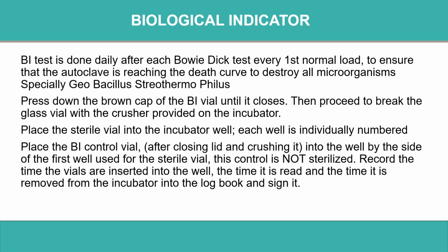After that, record the time the vials are inserted into the well. Actually, incubators have different times to show the result. Like we are using a 1 hour incubator; it will show the result after 1 hour. But in other areas, other hospitals, some are using 3 hours, some are using 8 hours. So it depends on the incubator and it depends on the vial, which vial we are using.